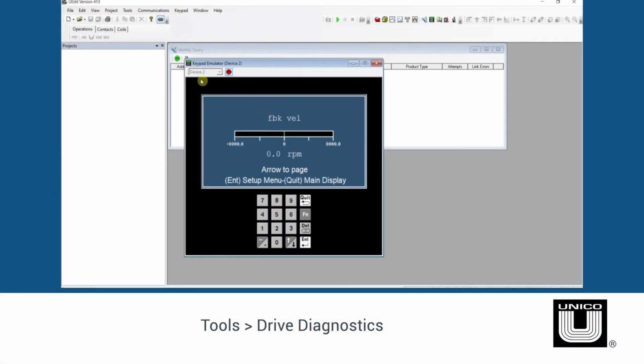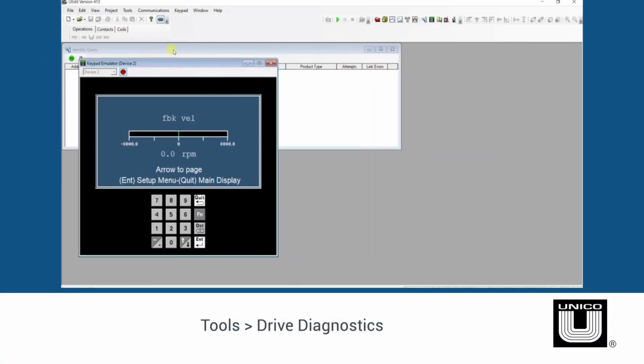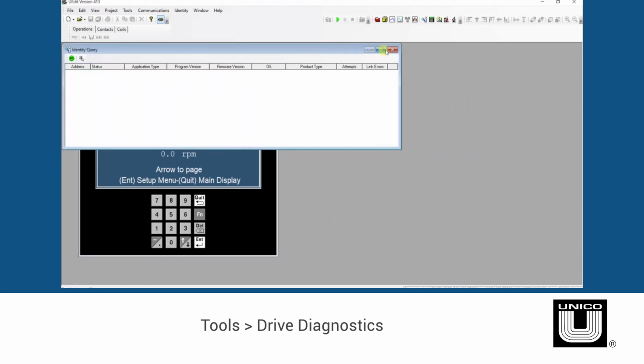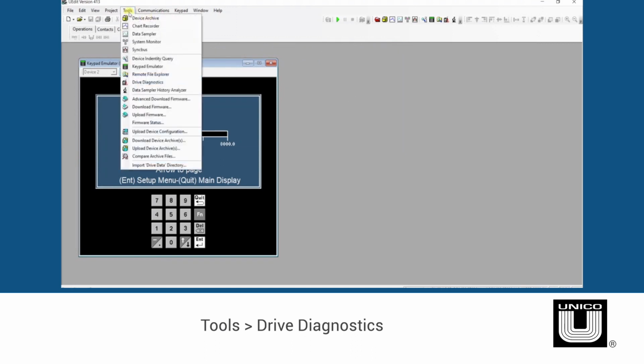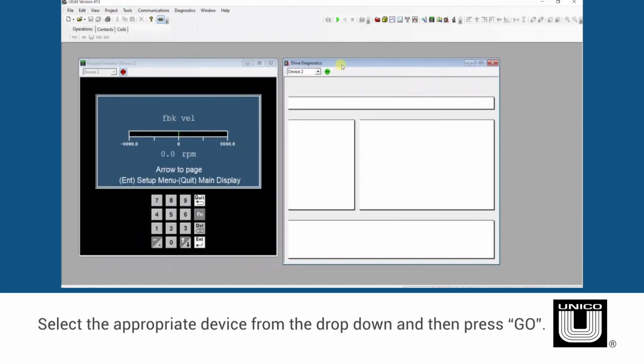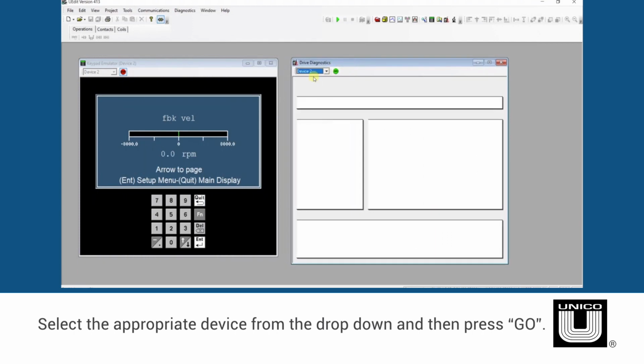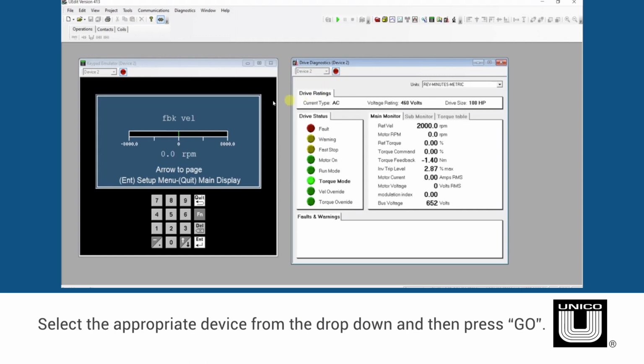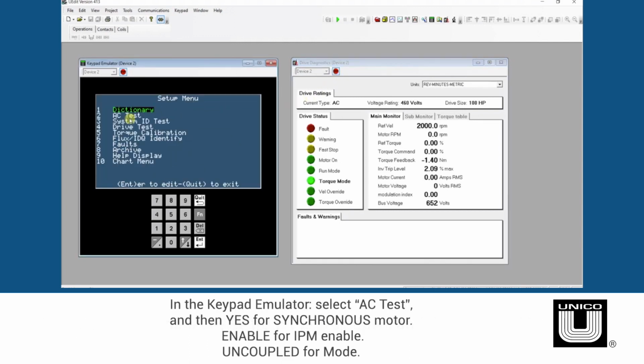The next step is to perform the AC test for the IPM motor. But first, I'm going to open the drive diagnostic window. To do this, go to Tools, Drive Diagnostics, and select the appropriate device. Then select Go to view basic information about the drive and IPM motor. Now we will begin the AC test.